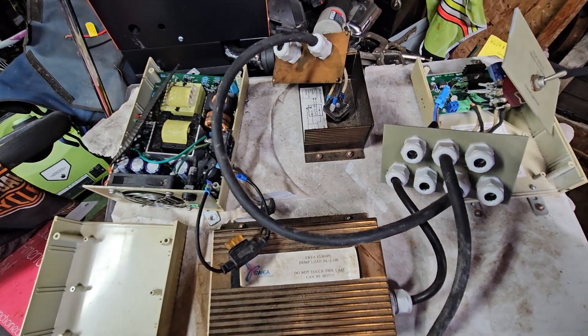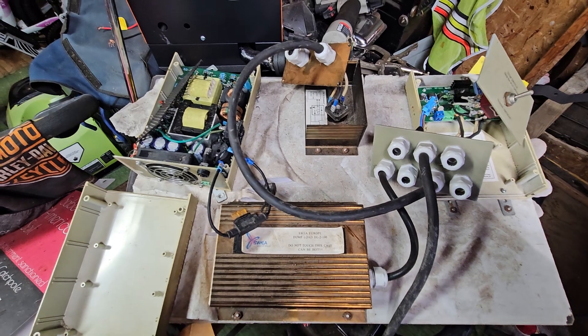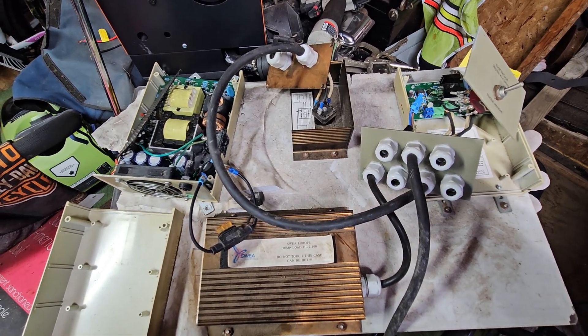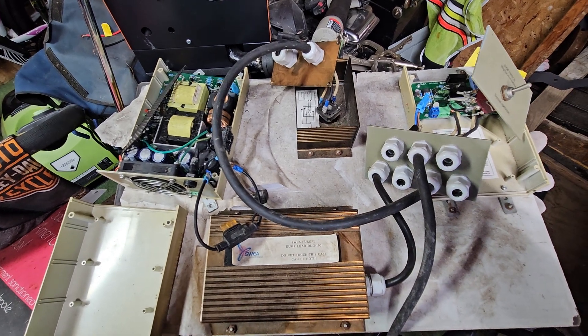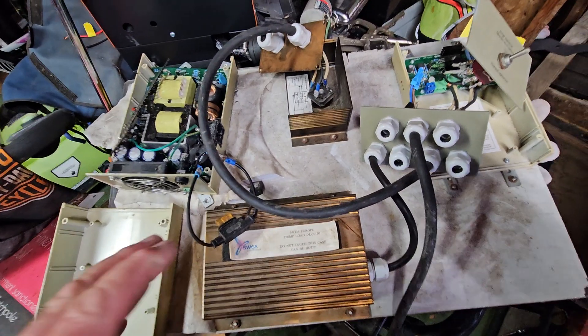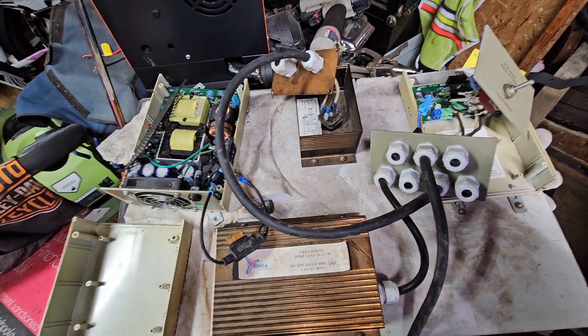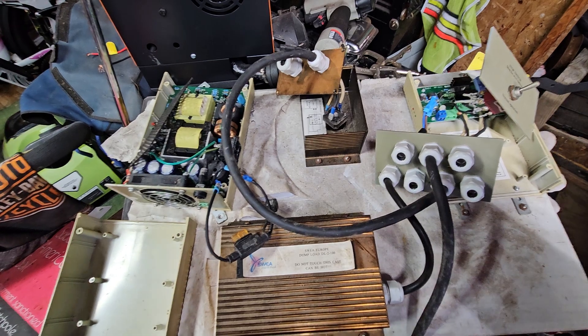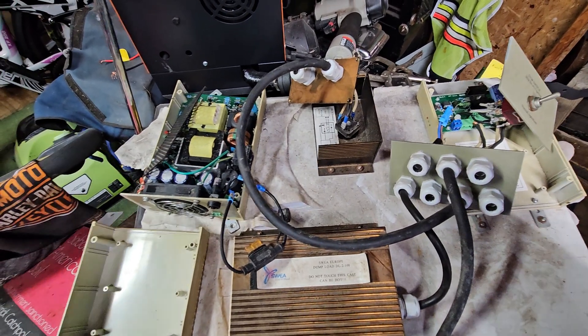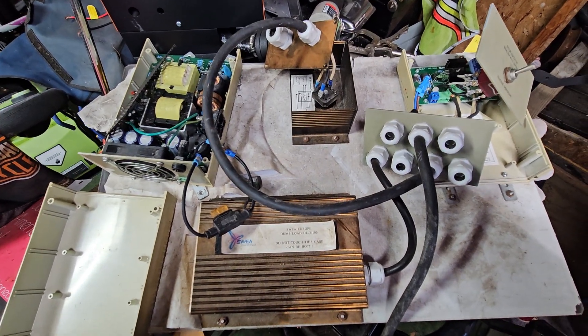SWEA in the Netherlands is a good company. When I bought these they weren't UL listed, so we really couldn't sell these here in the states. As long as there's a 110 or 220 connected to this, or my wind turbine on my shed, the power stays on. As soon as the power goes out, they quit producing power, so the linemen down the road don't get electrocuted — it's a safety feature.